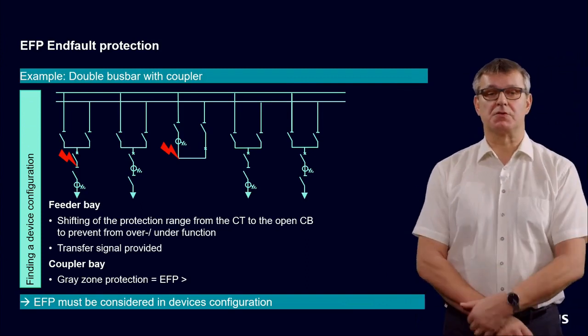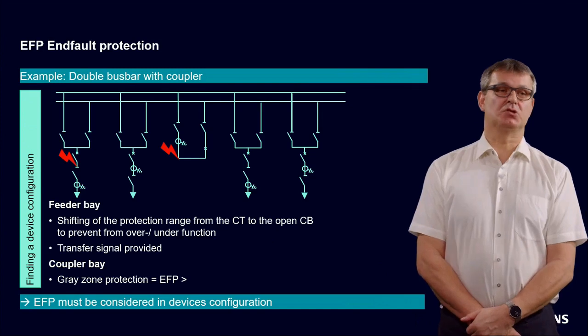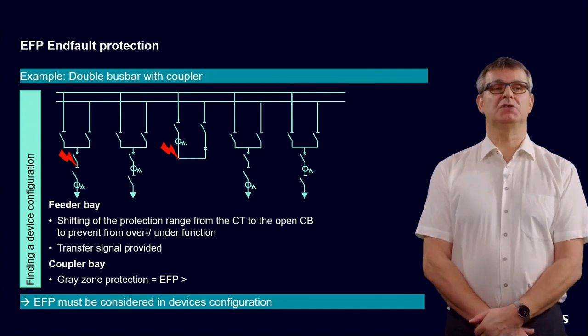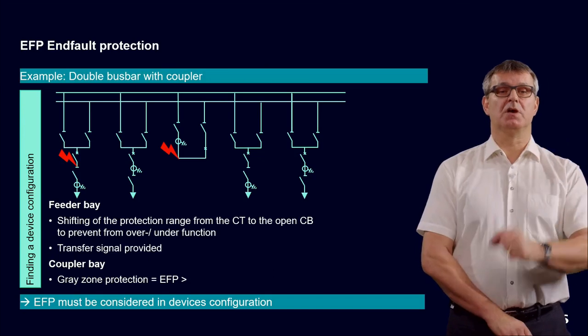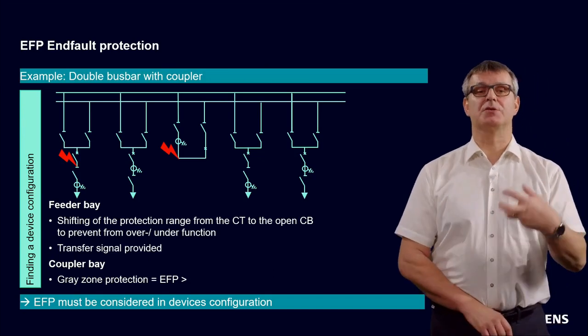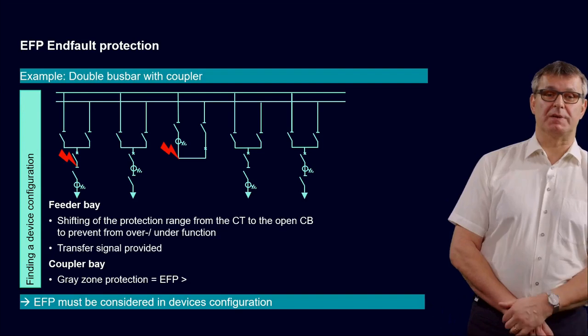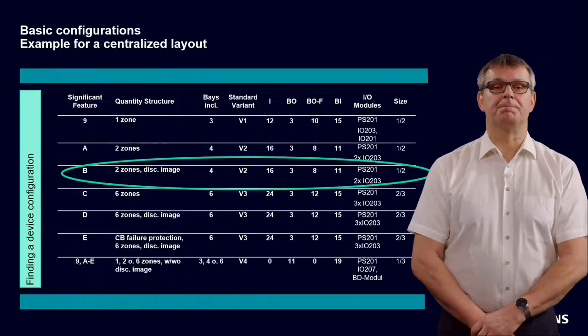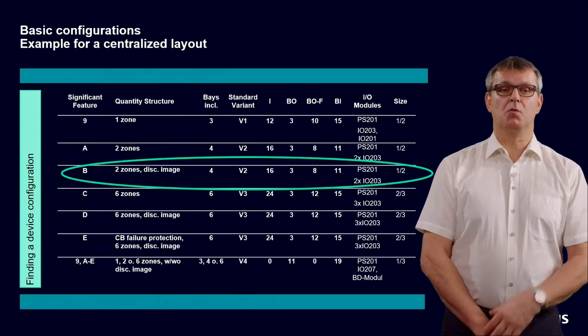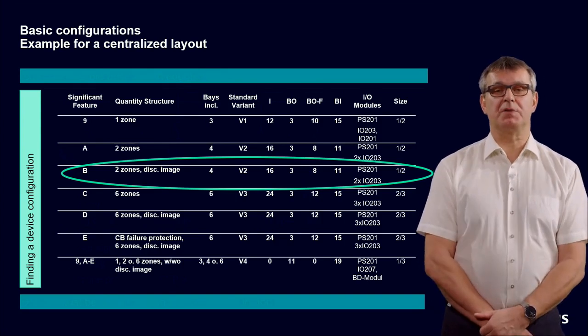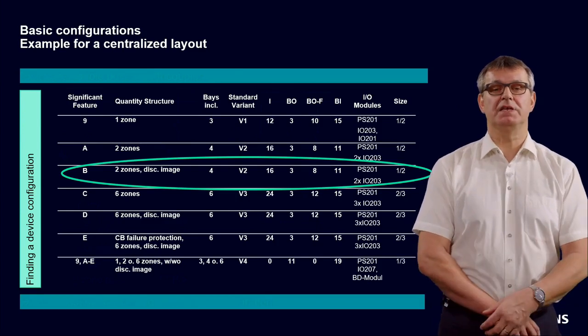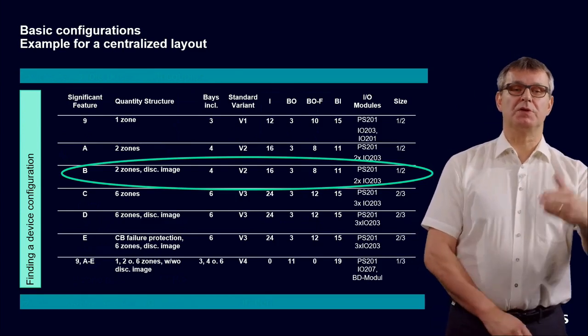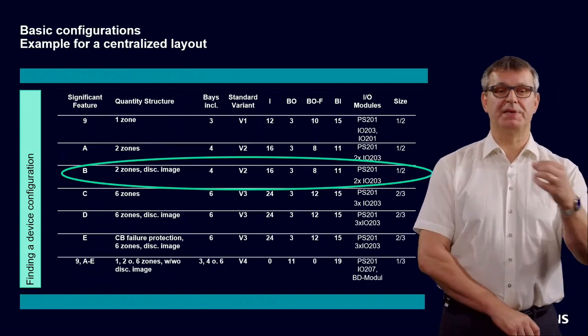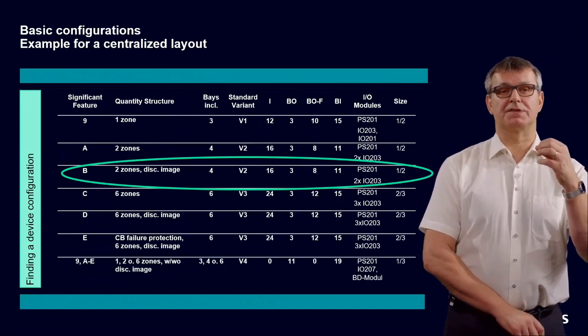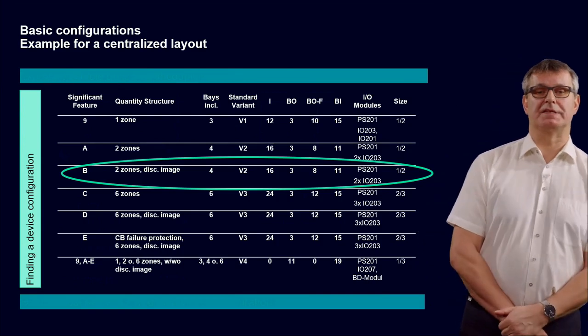So this means also in this case, we should consider one end-fault protection in each feeder bay, and very important, also one end-fault protection for the gray zone protection in the coupler. Okay, we have learned now we have this example of a double bus bar with 4 feeders and one coupler with 1 CT. And the proposal is that we can use a significant feature B, which delivers us 2 zones. That's enough for our example.